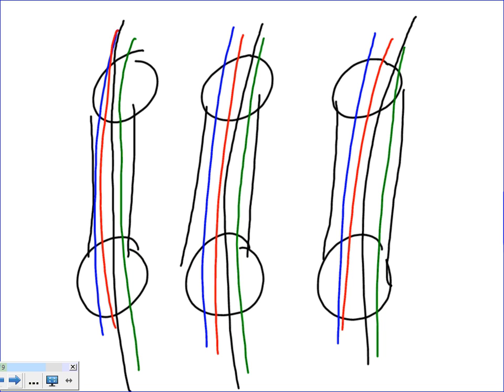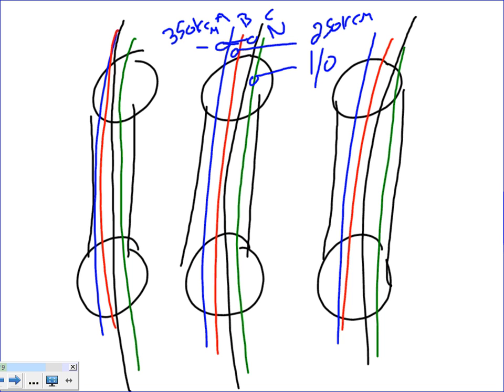Three sets, and just to put the numbers on them so it doesn't confuse us. Let's say this is A, B, C, and a neutral. So if I want to put numbers on just one of them, you take the A and the C. You remember that? What size AC did we say? 350 kcmil. And B was 250 kcmil. And N was 1 aught. These are typical for all three of them.